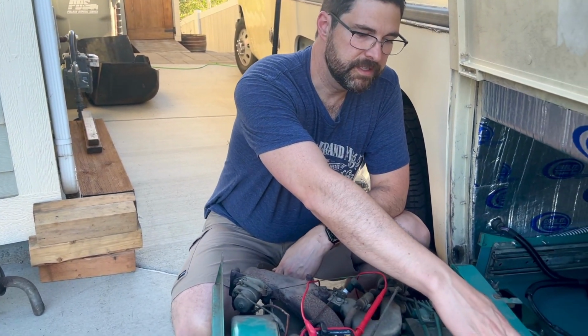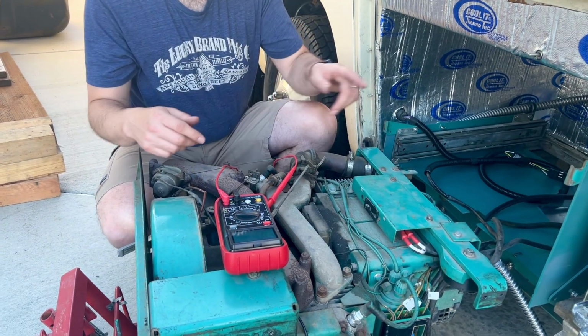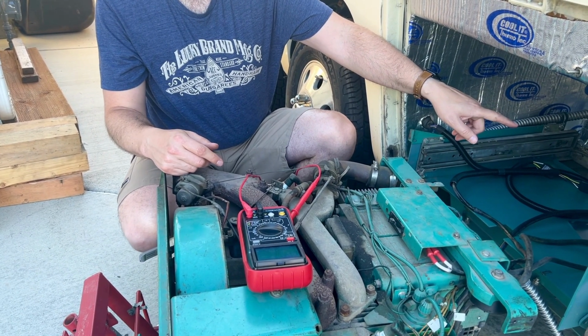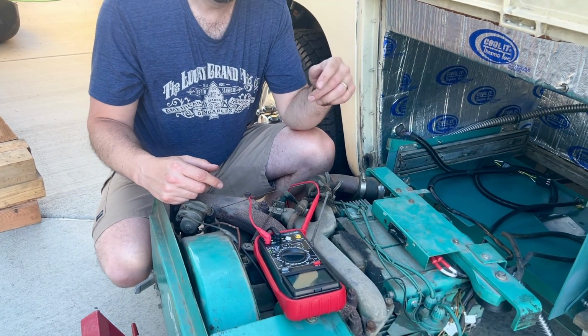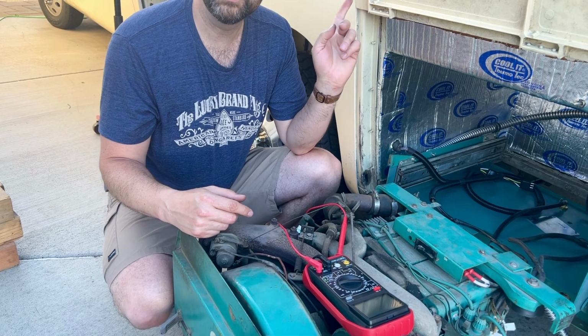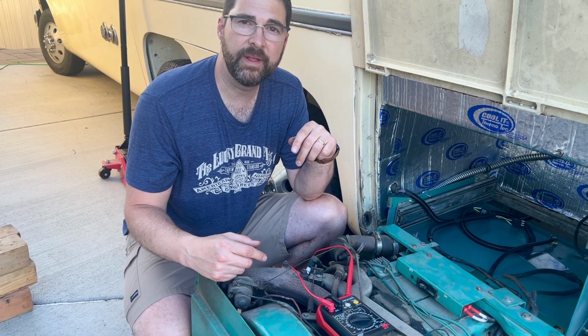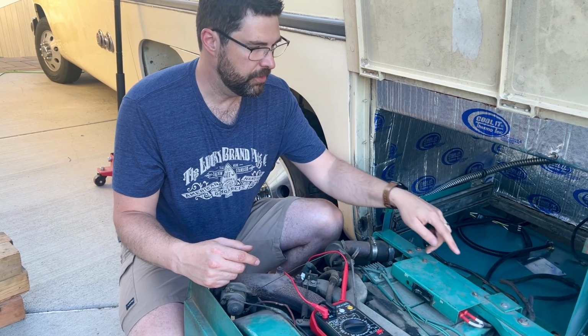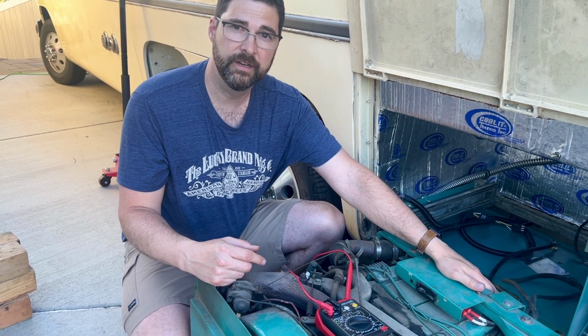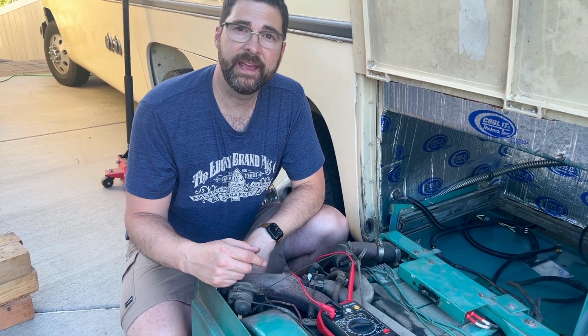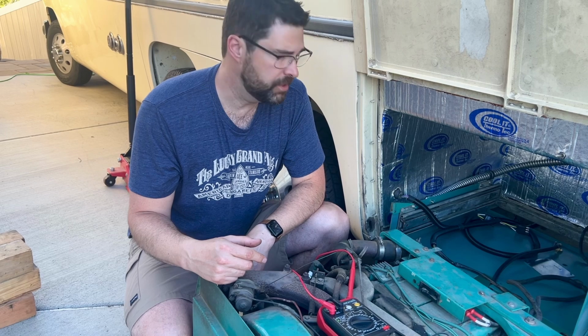So we can start wiring the actual AC into the coach. Up at the electrical box, there are 2 white wires and 2 black wires. The black wires need to be connected to this wire coming off the circuit breaker. It's hard to tell which is which on this end where the box is, so I'll need to do some testing to see which wire coming from the socket is the black and which is the white. Then I'll know which way to connect these wires, and I'll make those connections at the AC electrical box at the back of the cubicle.